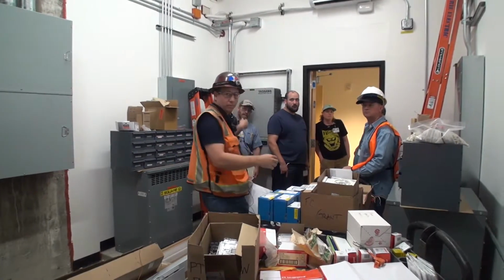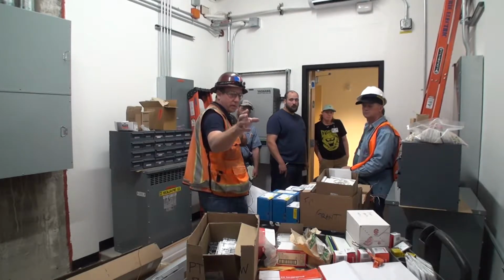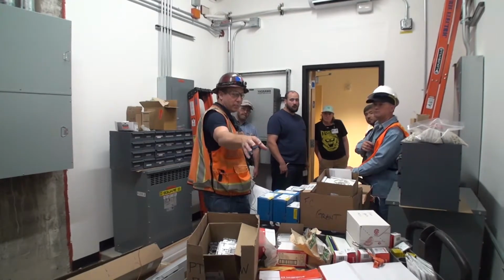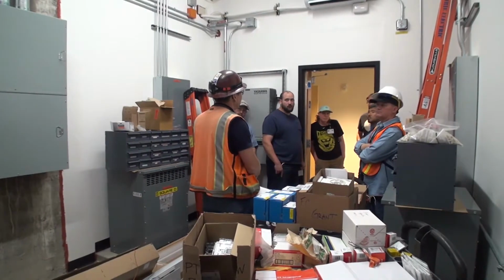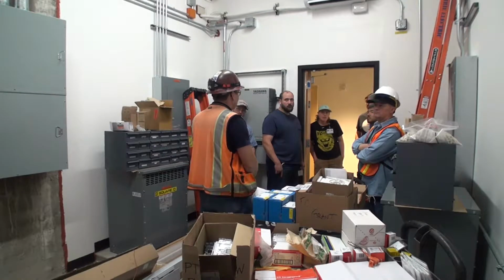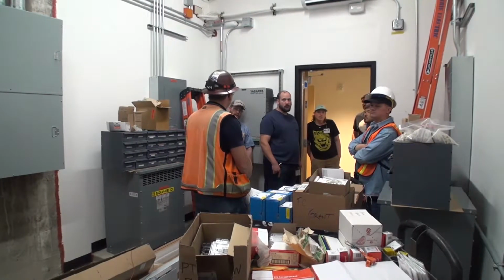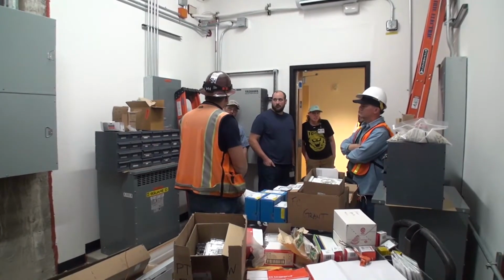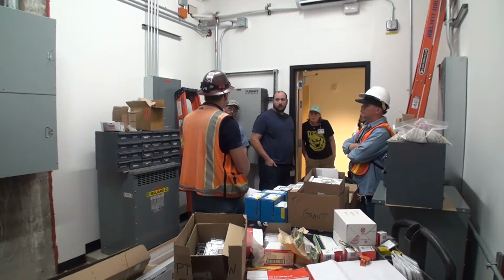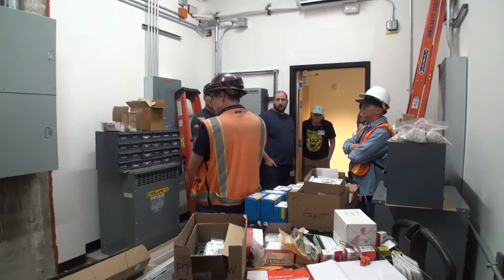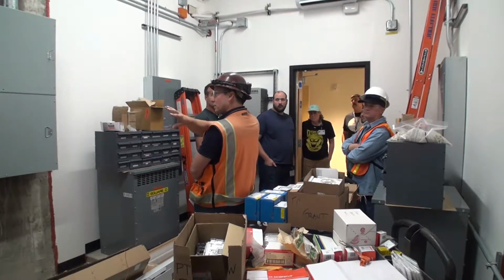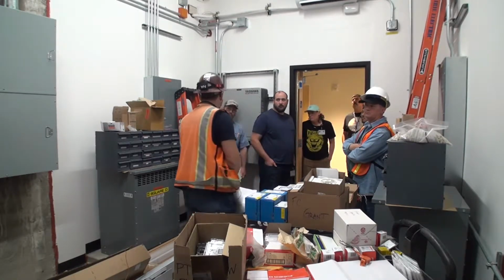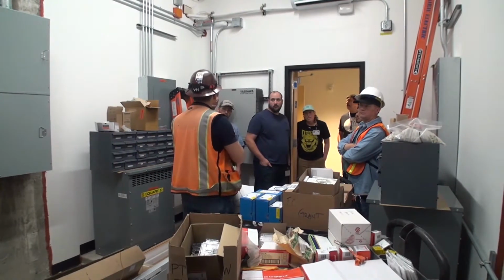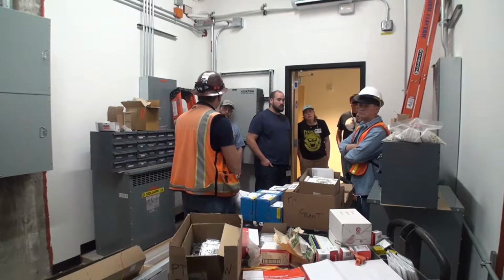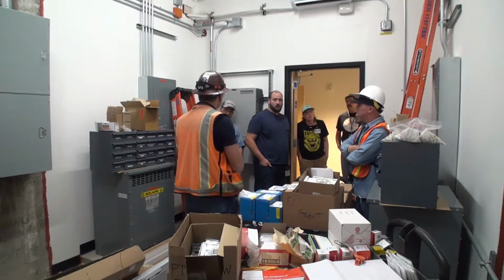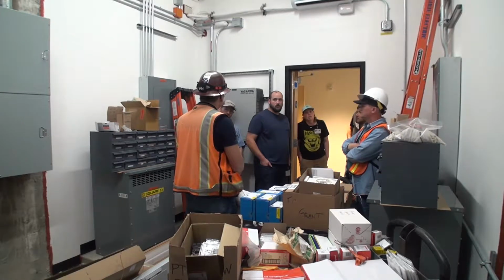The standby load, I think it's a 150 amp service, with a lot bigger panels for selective coordination so we won't get any nuisance tripping. It is really a light load. I mean, it's really feeding 120 volt plugs in the IDF rooms. That's it. Well, what's the purpose of having both emergency and standby? Code requires the emergency system. Once there's a coordination study, they don't nuisance trip. But once we leave and go through the transfer switch, we need the emergency on its own. It can't feed any non-emergency systems. And then the standby is like a supplemental load after the emergency loads have been satisfied? Is that the reason?